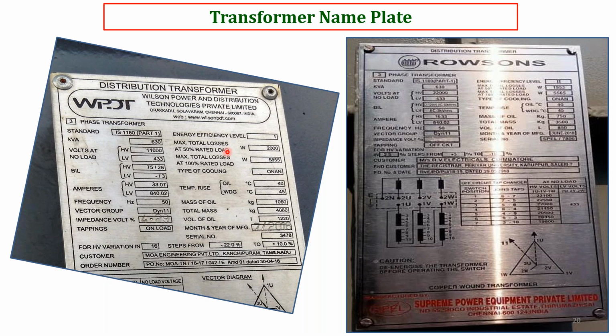Suppose you increase the transformer loading to near 100%, then the self loss of the transformer is going to be almost 6 kilowatt. That's why I told you, when you increase the loading percentage, the self loss of the transformer also increases. So it is advisable to operate your transformer at nearly 40 to 60%, which will consume less energy for the transformer.